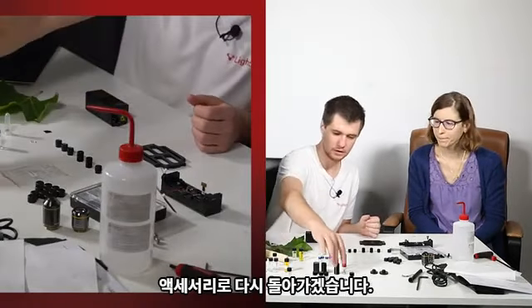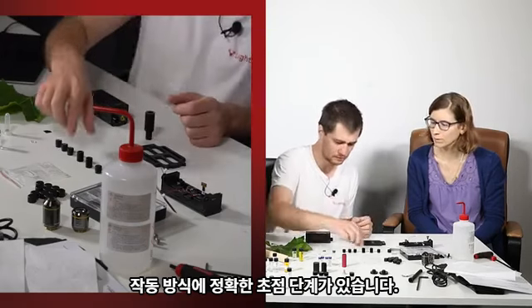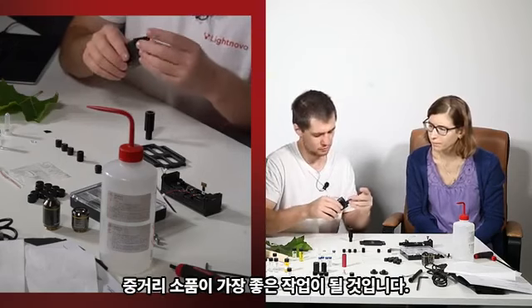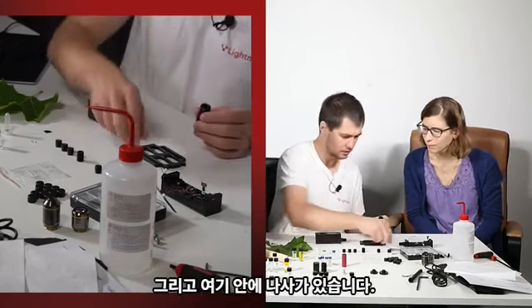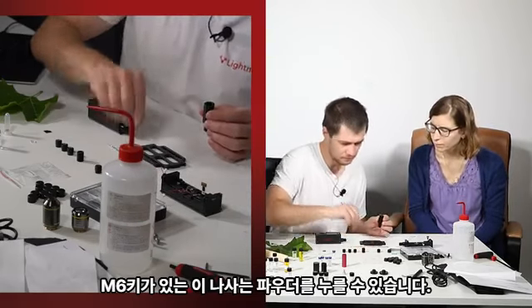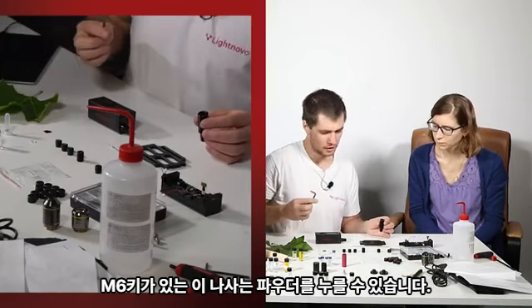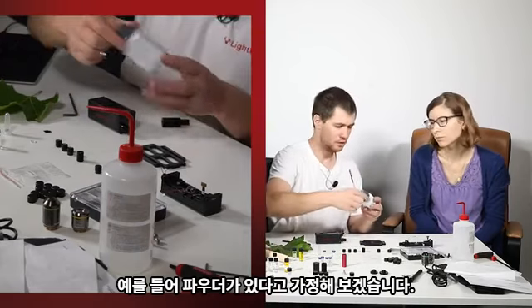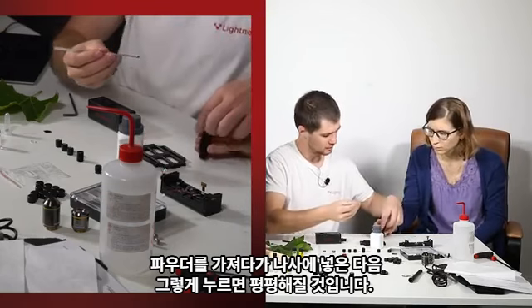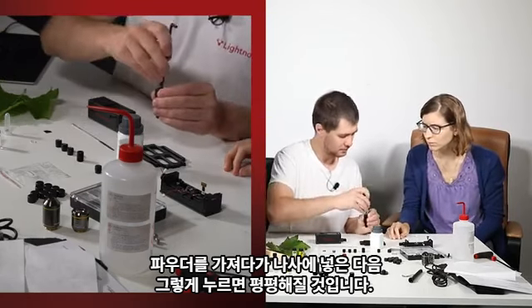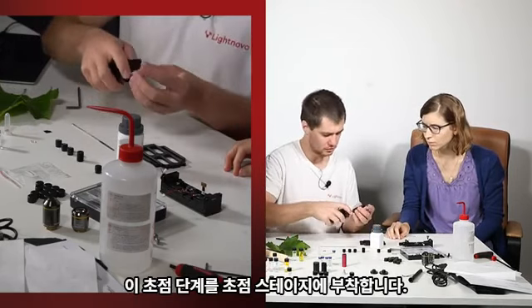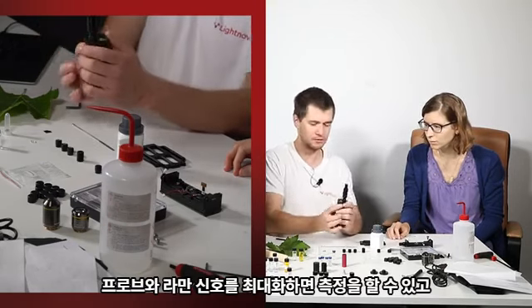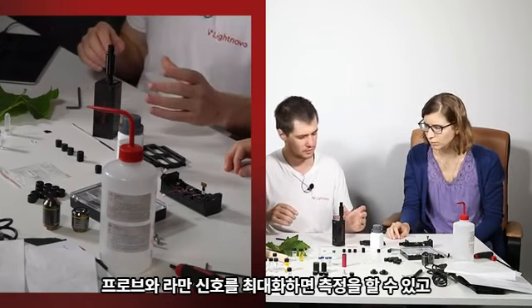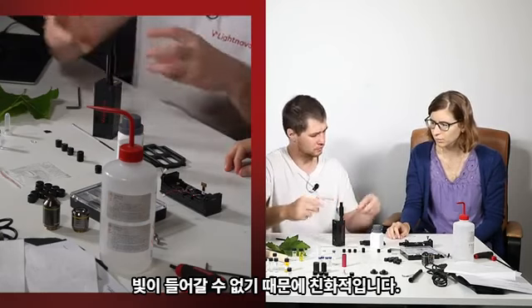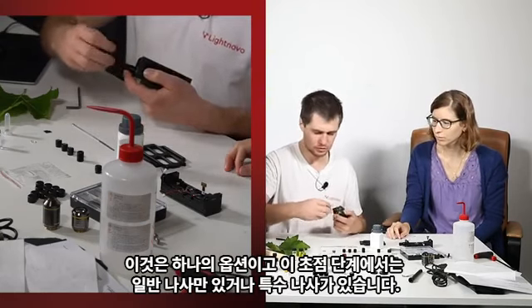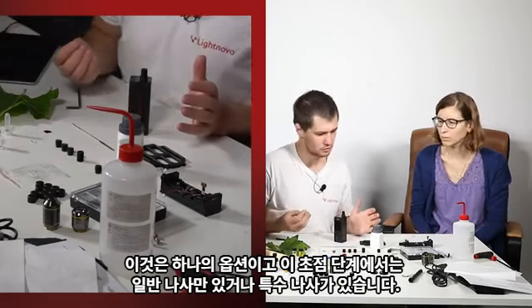Let's move back to accessories. Okay, there is a precise focusing stage. How does it work? Let's say you have some kind of probe, the middle distance probe would be the best. And then inside here you have a screw. In this screw, with an M6 key, you can press some powder. Let's say we have a powder, you take it, and you place it in the screw, and then you press like that, and it will be flat. And then you attach this focusing stage to your probe, and maximizing the Raman signal, you can do measurements, also environmental free, because no light can go in.